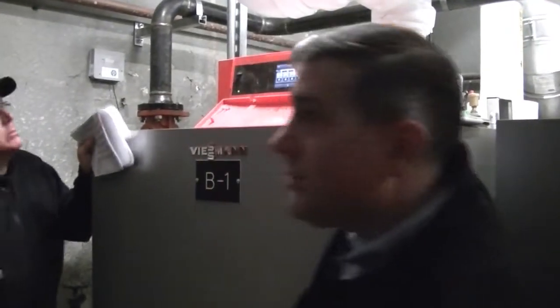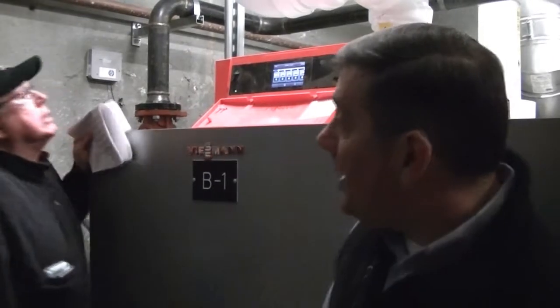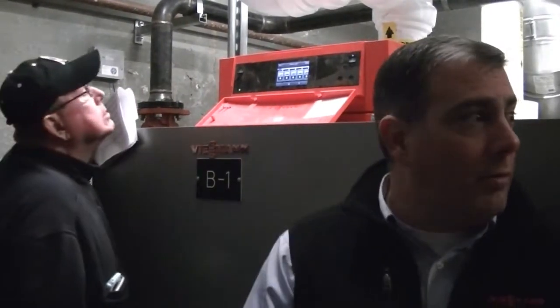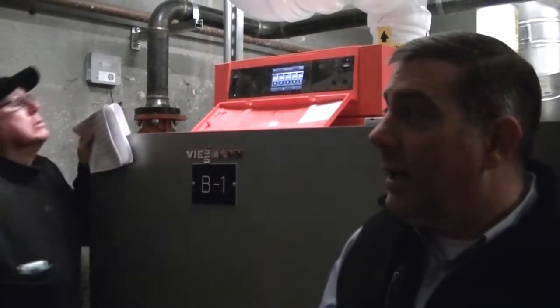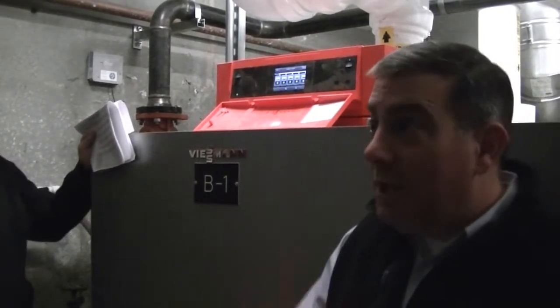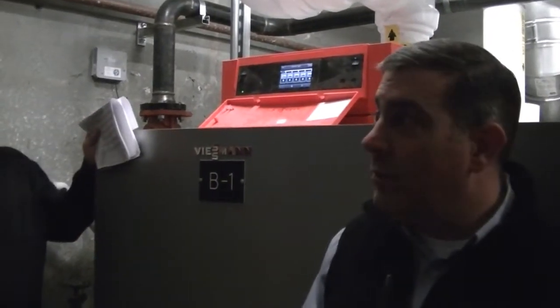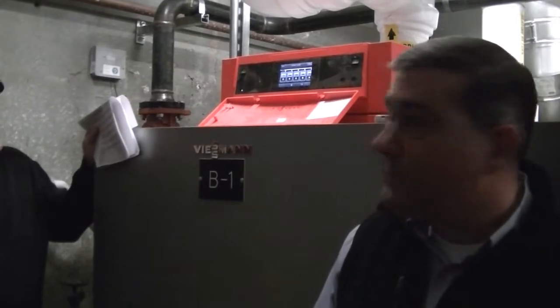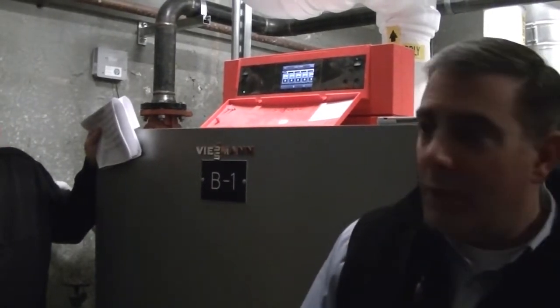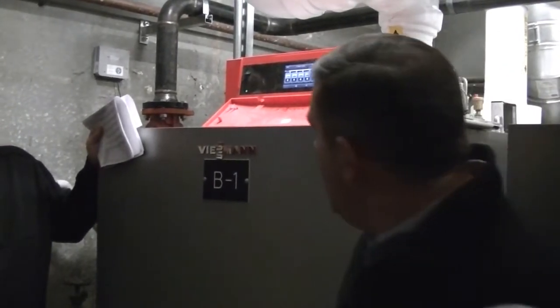So you may come back next month and number 3 is all the way on the other side of the road. Okay? Now if any one of these locks out or has a burner failure or something like that, it will become out of rotation. The next boiler in line will step up and be the next boiler in line until you solve that problem. Okay? So let's talk about faults for a minute.